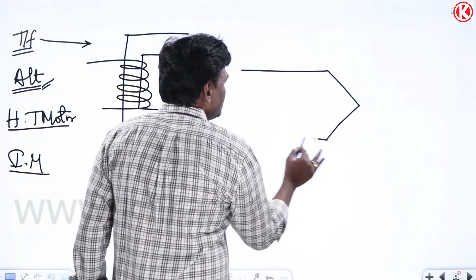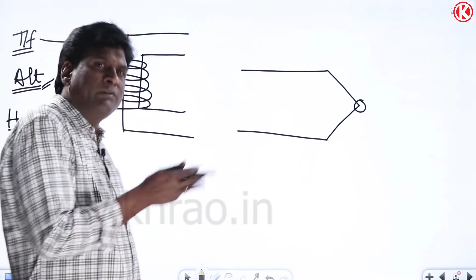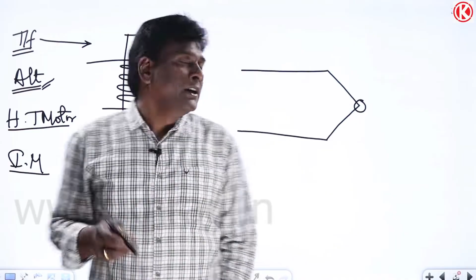Okay, alternator winding will have forward conductor, back-to-back return conductor. And here if you observe, sharp edge is there. So the moment sharp edge is there and voltage levels are 11 kV or 12 kV or maximum up to 18 kV, voltages are significant, but sharp edge is there. That's the point of interest.